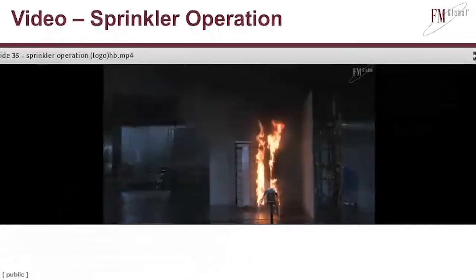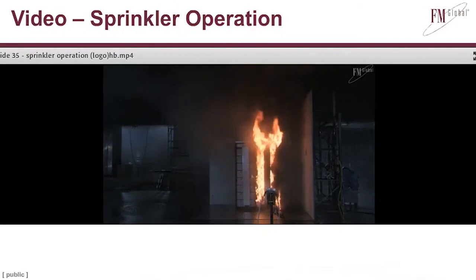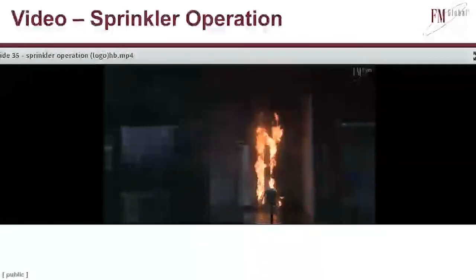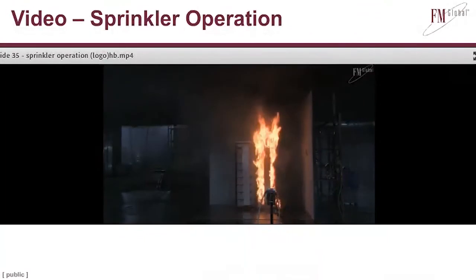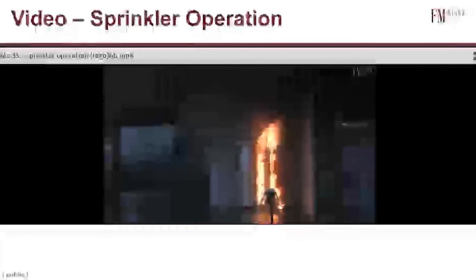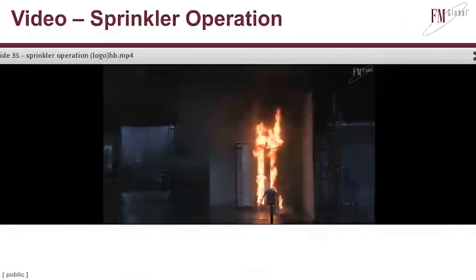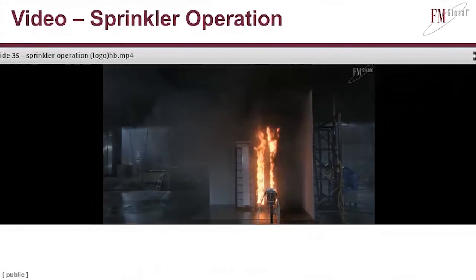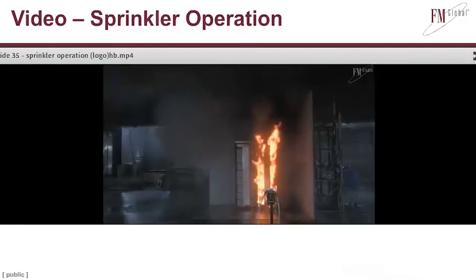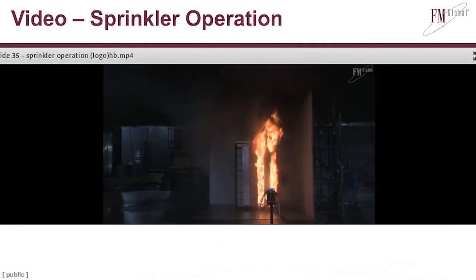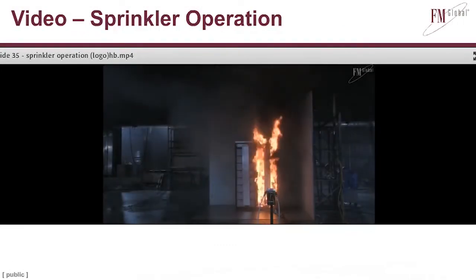And as you can see here, and this will sort of be a theme going forward, the sprinkler protection doesn't really reduce, doesn't suppress the fire, I'll say. But one thing that I was really surprised at is how good of a job it can do at keeping the fire from spreading from one rack to the next. And we'll talk about that more in one of the upcoming slides. I just want to jump ahead a little bit here and show you about 3 minutes after that sprinkler operates. You can see the fire continues burning quite well.